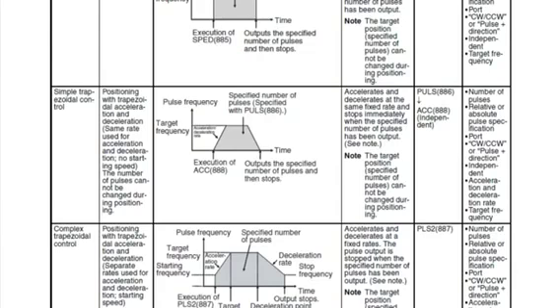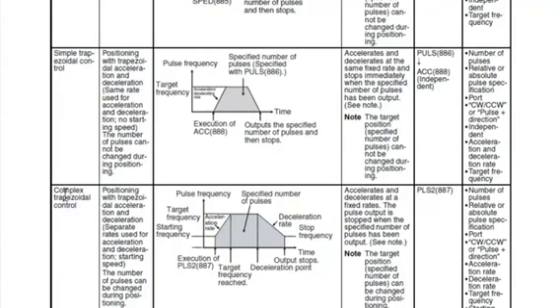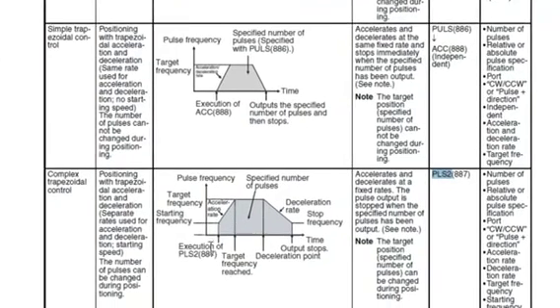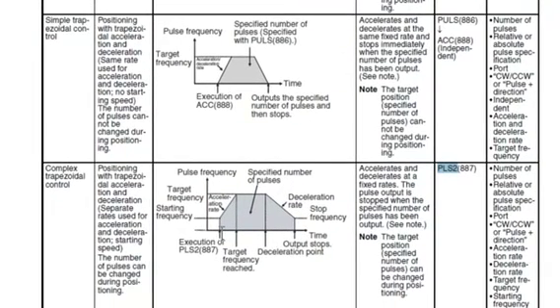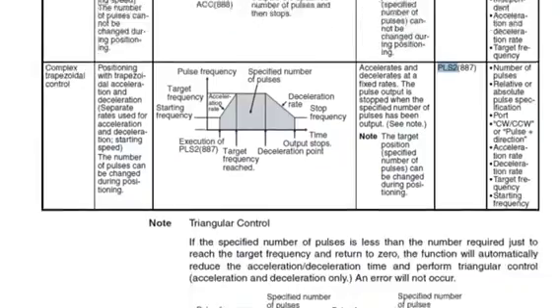The positioning commands are really done with a combination of some pulse commands and so forth. There's some more detail on how to stop motion if it's running under a speed command, and or doing that with a ramp down. Scanning down, you'll see the pulse output for more doing positioning. You can use a pulse command and or a combination of a pulse command and an ACC command to get ramping to do more of a trapezoidal move. And the complex trapezoidal moves can be done very nicely with a pulse two command. This is the one I prefer actually, all in one instruction.